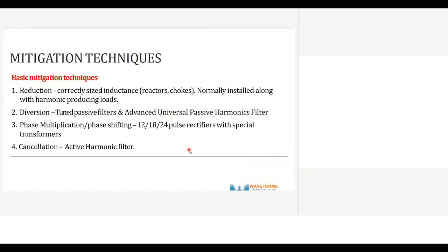So one thing is reduction. We call it reduction because correctly sized inductance is normally installed along with harmonic producing loads. Typically the devices all come with reactors. The problem is they come with 3% and 5% impedance, but you can't have higher impedance because the voltage can drop. If the voltage drops, the drives will trip. So you'll have to size them properly. You can use only 3% or maximum 5%. If you use the 5%, the shifting is better.